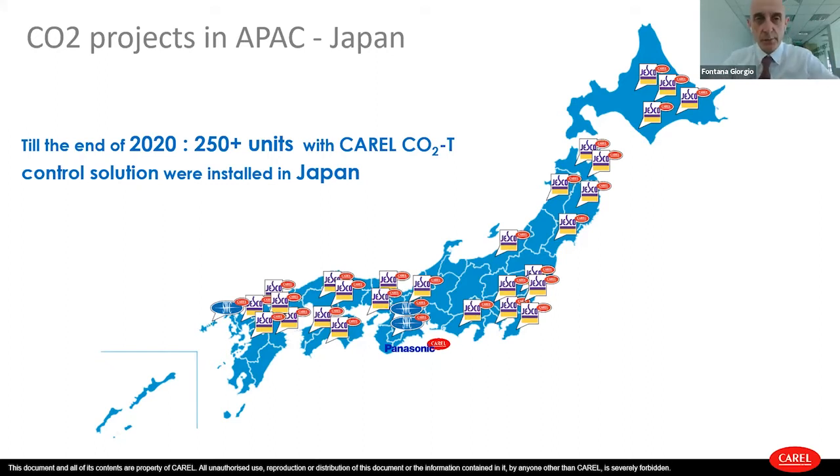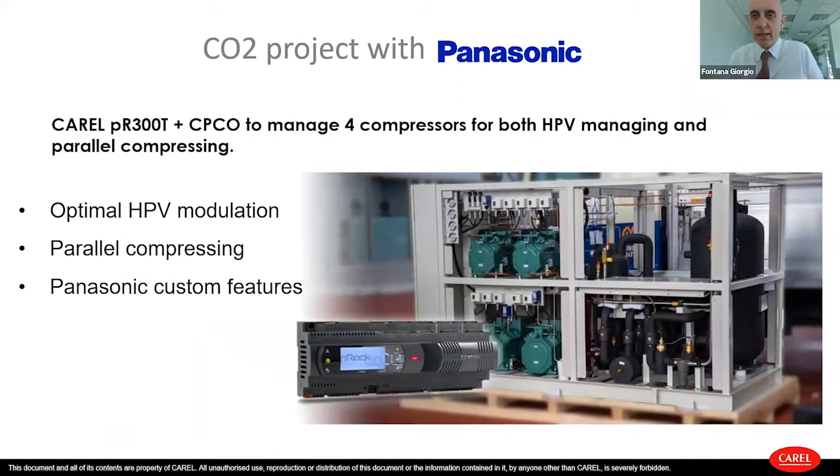In Japan, we have more than 250 units with our CO2 transcritical application. We are working in partnership with Panasonic Appliances for CO2 transcritical rack. There was also a recent installation at the end of last year in one of the big cold rooms in Osaka for fish stocking and processing. Using our technology — our controller called the pRack CO2 transcritical — implementing eco functions like parallel compression and modulation of the high pressure valve, which is the valve on the outlet of the gas cooler.